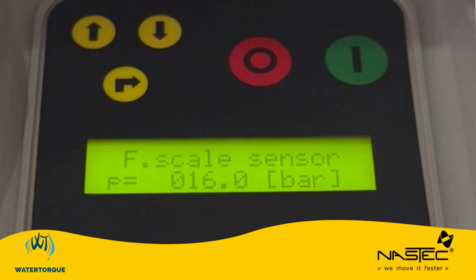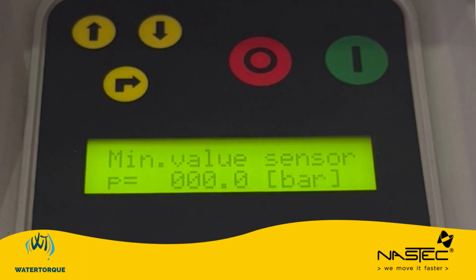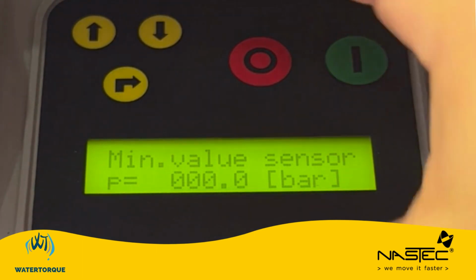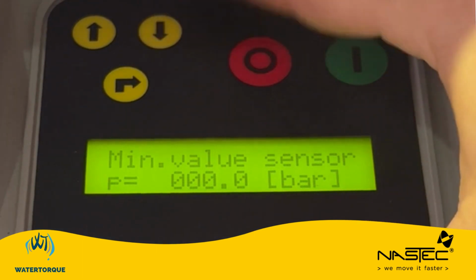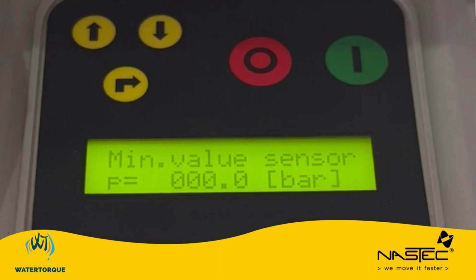Next one down is F-scale sensor. This refers again to our pressure transducer. This particular setup has a 0 to 16 bar pressure transducer. That's on the high end, the maximum, and this is on the low end, so 0 to 16. We would leave that as is, but you want to make sure that you are inputting the correct value on what is on your pressure transducer.